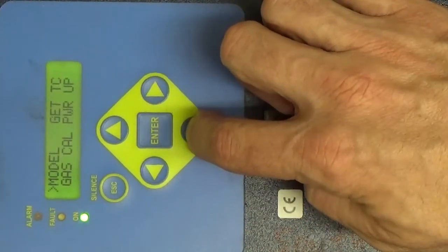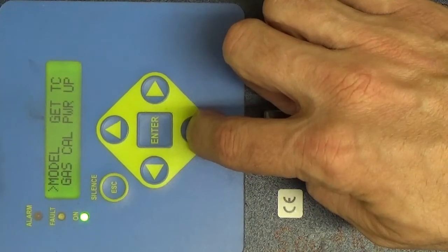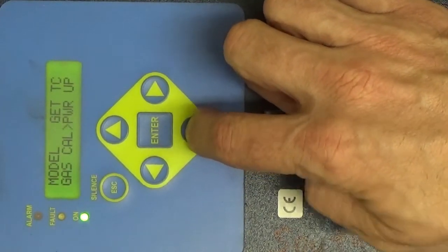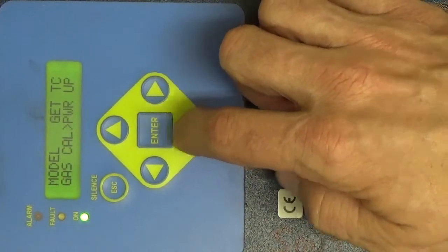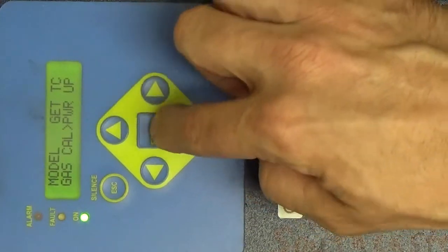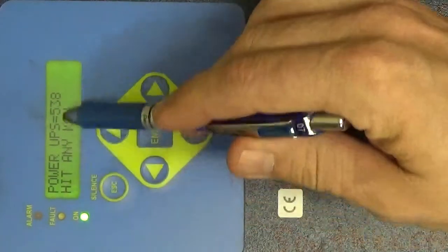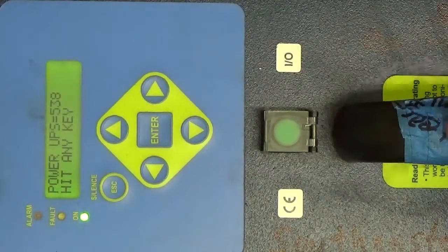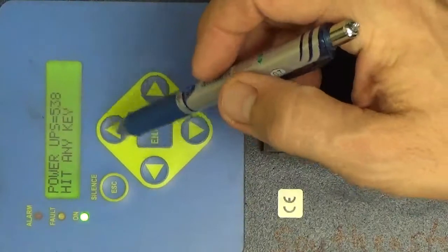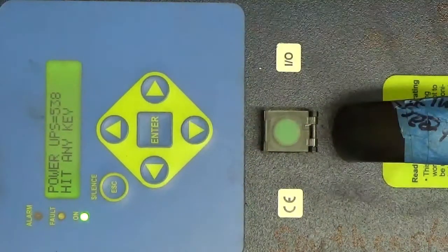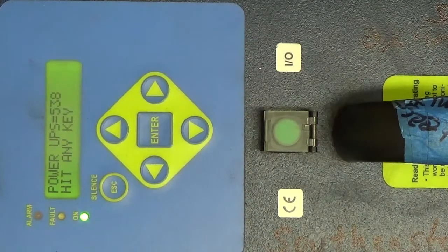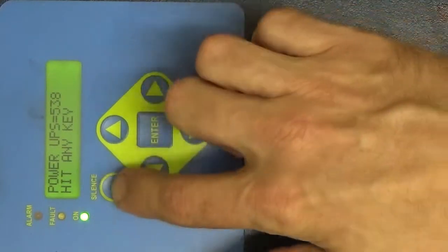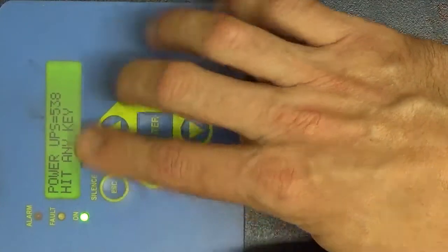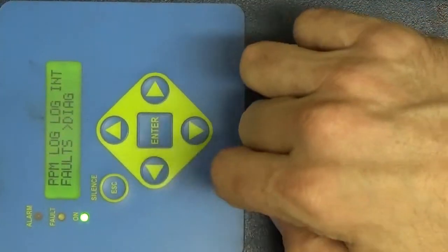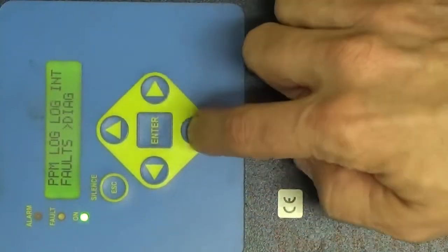Other things that are in the second level menu is where you could control the model unit. The other thing that's interesting to record, that I like to record, is something called power up, PWR-UP, and this will tell us how many times the unit has been started and stopped since its last calibration. This particular one shows 538 starts, which means this unit has quite a bit of use since its last calibration. Sometimes you see numbers as low as 20, sometimes you see 500. So we hit escape twice, and that'll bring us back to the main menu.